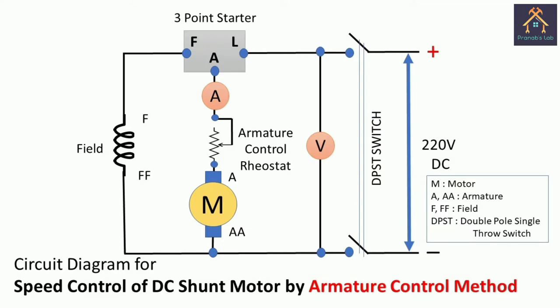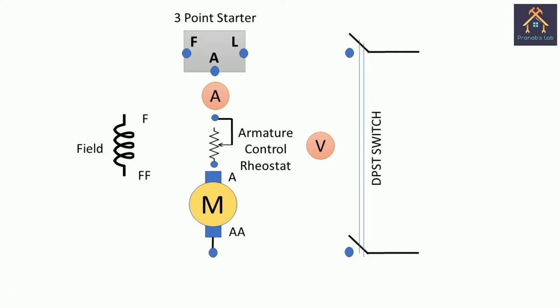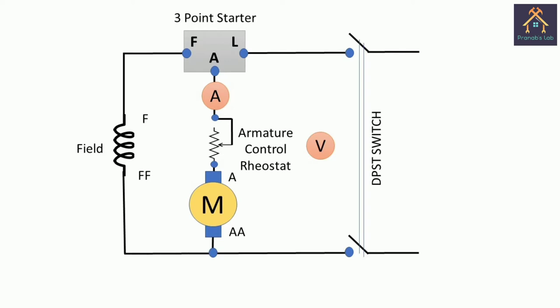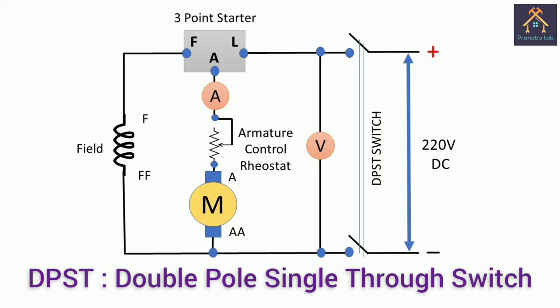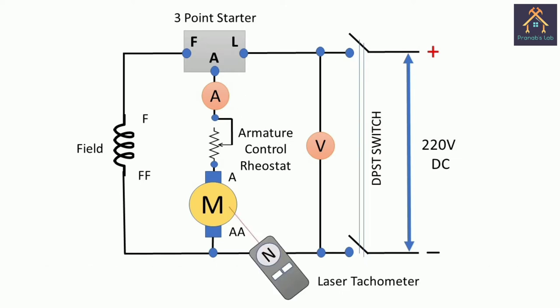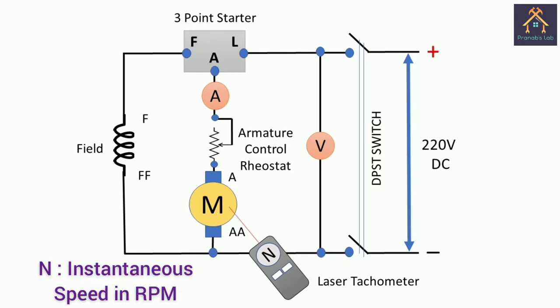Before performing the test, let's discuss the circuit diagram for the test. You can see the required circuit diagram. The L terminal of the starter is connected with the line positive. Then, the A terminal is connected with armature terminal A through the ammeter and armature control rheostat. The F terminal of the starter is connected with field terminal F. The double F and double A terminals are shorted and connected with supply negative terminal. We can connect a voltmeter to measure the supply voltage. A 220V DC supply is fed to the double pole single throw switch. The ammeter will read the current through the armature and a non-contact type laser tachometer will read the instantaneous speed of the motor.